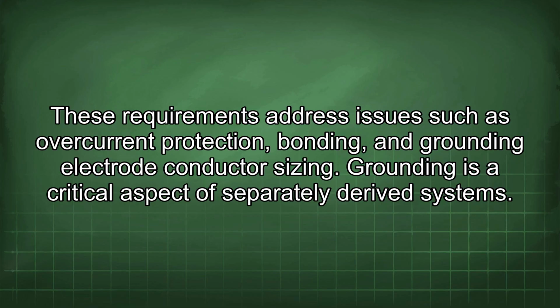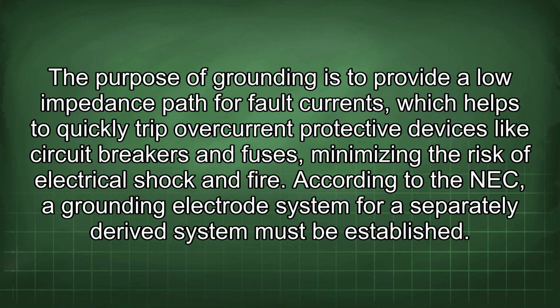Grounding is a critical aspect of separately derived systems. The purpose of grounding is to provide a low impedance path for fault currents, which helps to quickly trip overcurrent protective devices like circuit breakers and fuses, minimizing the risk of electrical shock and fire.